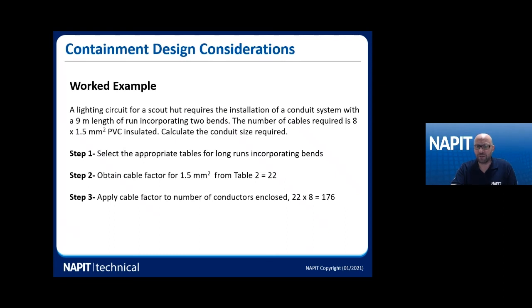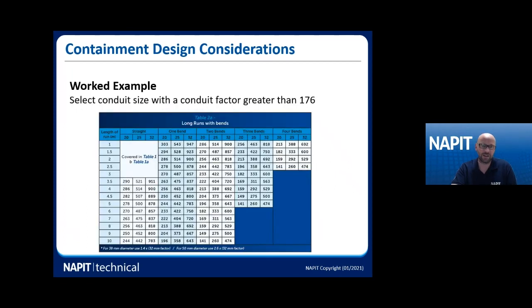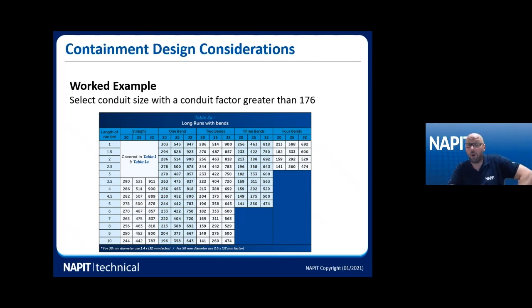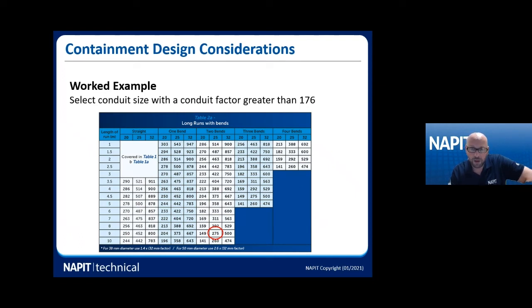Step three: apply the cable factor to the number of conductors — 22 × 8 = 176. Now select the conduit size with a conduit factor greater than 176. Looking along the nine-metre row, going across to the two-bend column, 176 is greater than what a 20mm conduit can take, so we move up to a 25mm conduit. That's how it's done — quite simply.